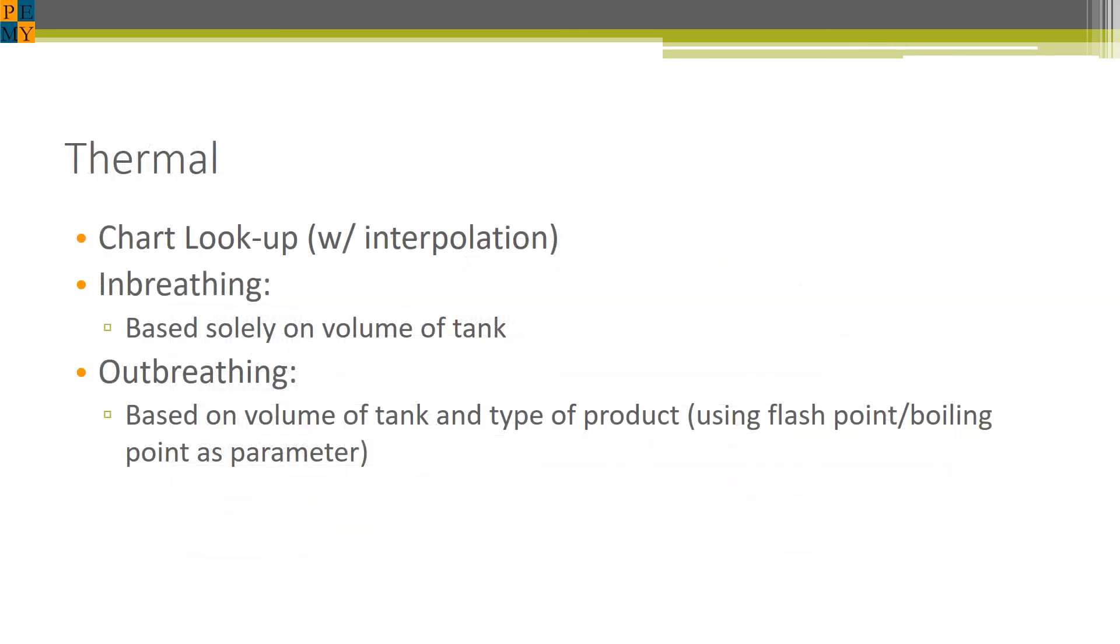For thermal effects, we essentially look up the value in a table where the input is really only dependent on the volume of the tank. The annex does not consider insulation or where the tank is located. For outbreathing, if the tank is volatile, there is also an additional factor to account for there. Based on these inputs, we look up the value in the table and that is the required flow rate necessary. For intermediate values that are between rows, one must interpolate between these values to find the actual flow rate necessary for thermal venting.